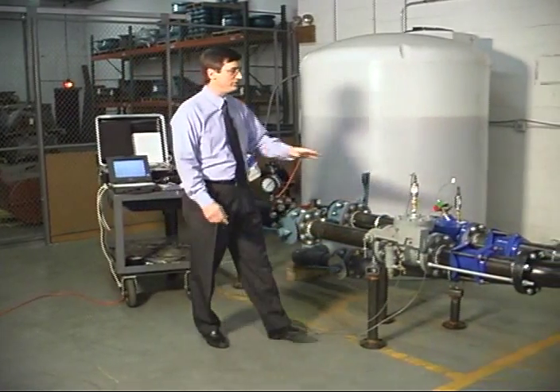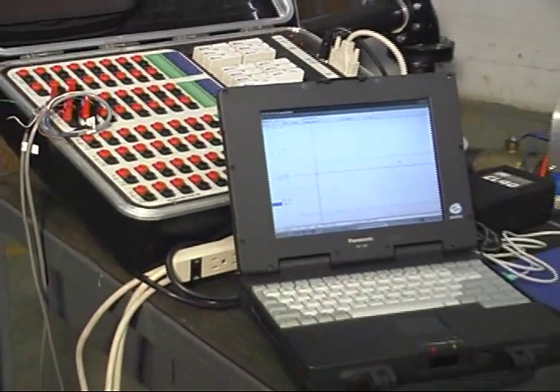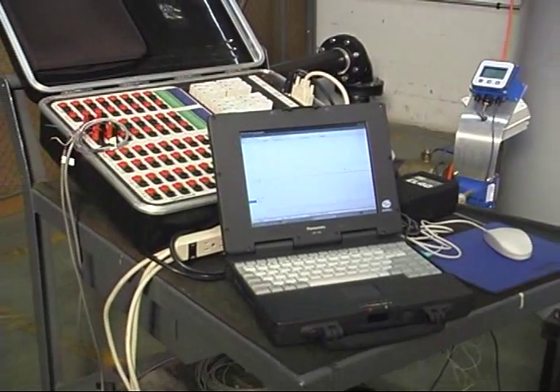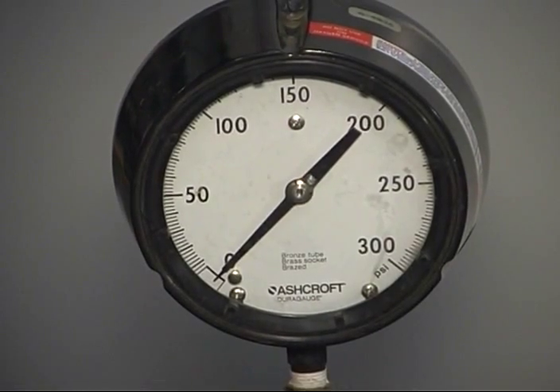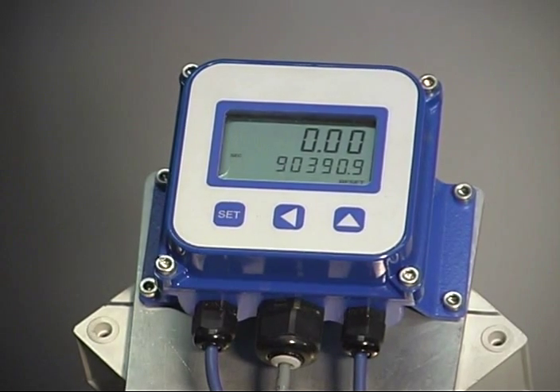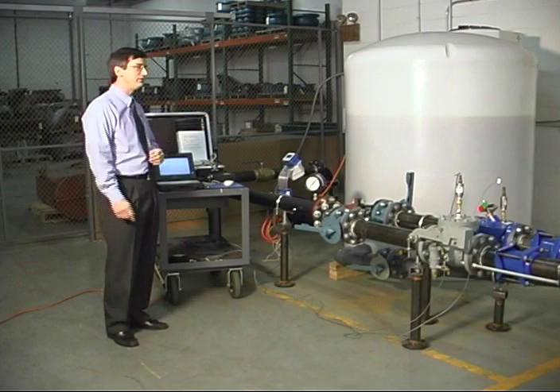Mounted on the top of each valve is a pressure transducer, which sends an electrical signal of the pressure back to a data acquisition system, which is a PC-based system which is going to record the pressures. We also monitor the pressure with a pressure gauge. We're also monitoring the flow velocity so that we can do subsequent calculations on the dynamics that are involved in the system.